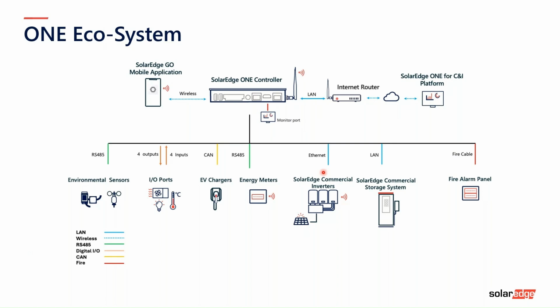So what we're trying to do is encourage people to put all the inverters, not just leader-follower but all of them, when we fit a ONE controller, onto the local network. So you can have a switch, so each of them becomes a leader. This means each inverter can get the information straight away rather than waiting for its leader to pass it on. You can still have them on RS485, so if you've got an existing site it will still work fine. But for future installations, we're saying let's look at having each inverter as a leader.